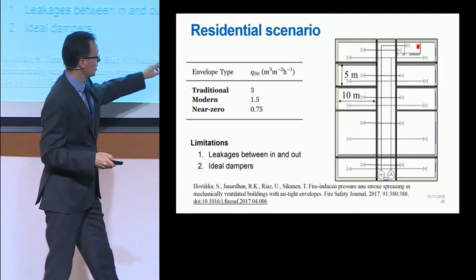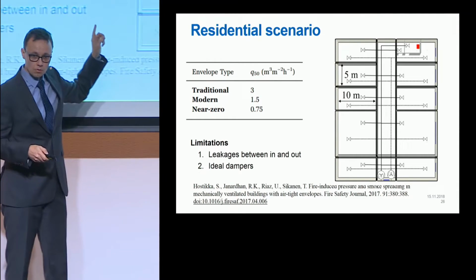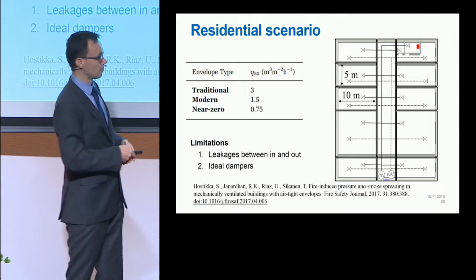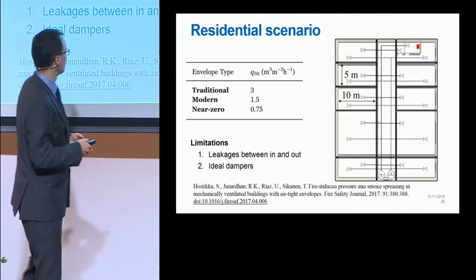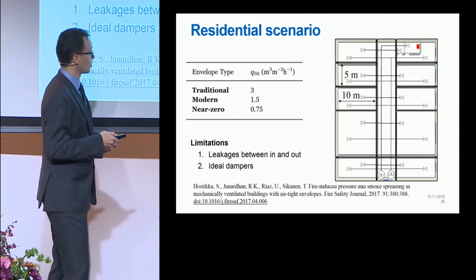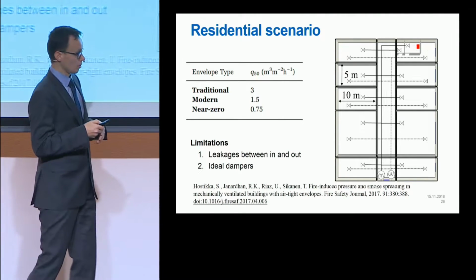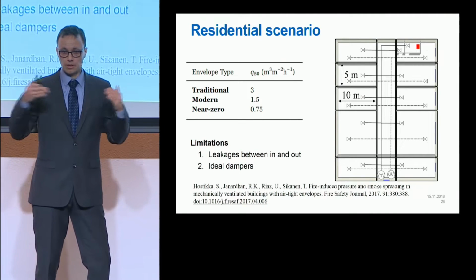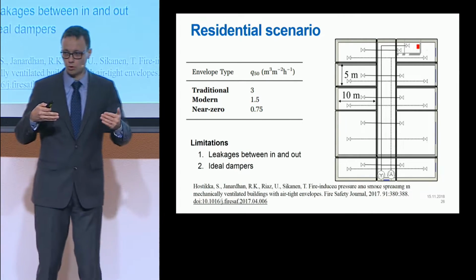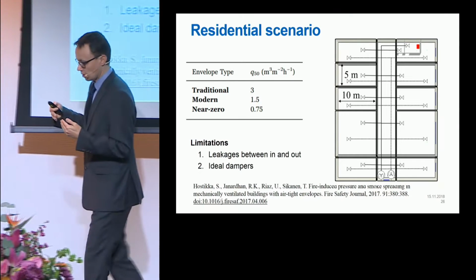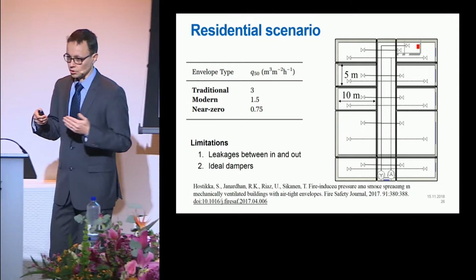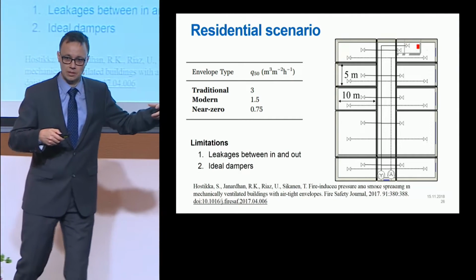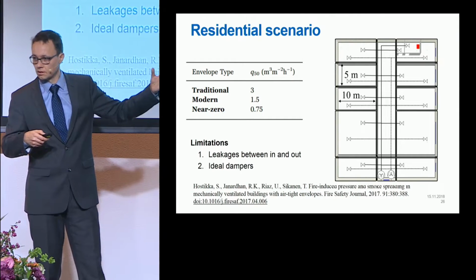The model includes the inflow and outflow ventilation networks with fans, possibly dampers, and so on. What's difficult is to accurately model the wall structures and leakages, because normally the airtightness measurement for such a building is made for the entire building.